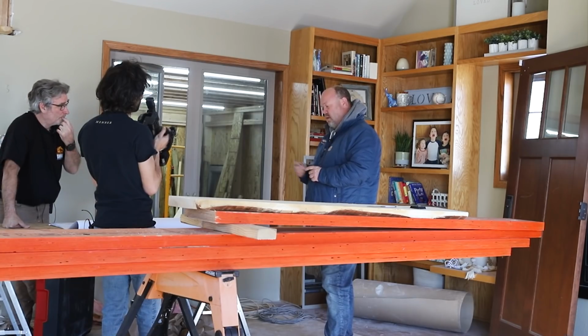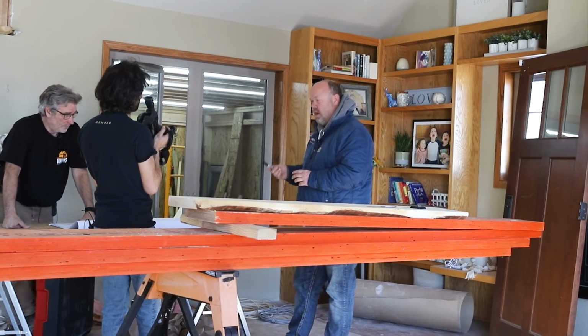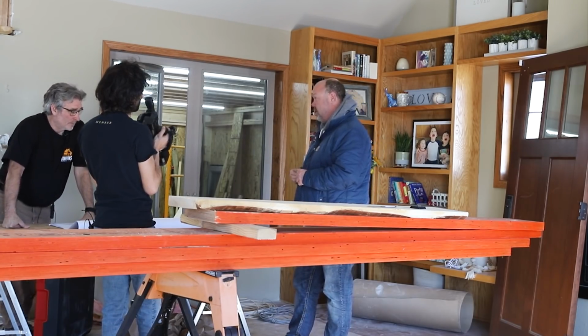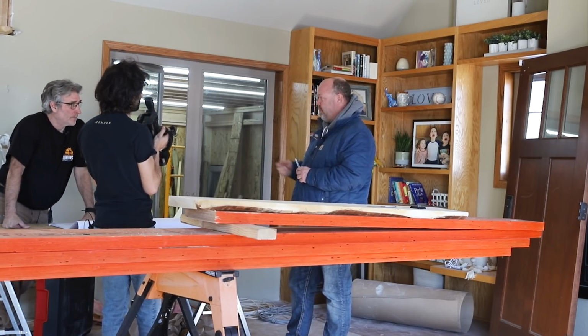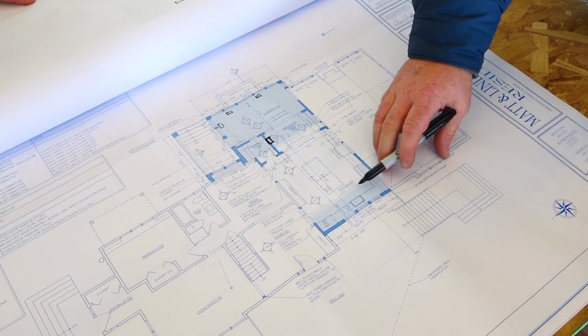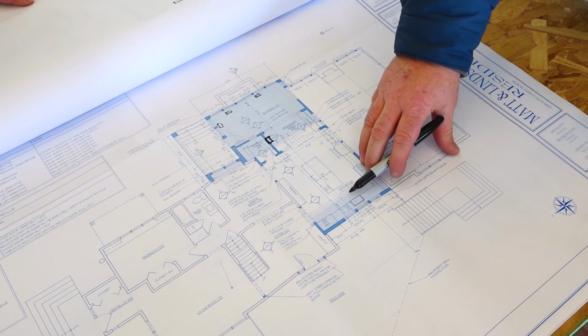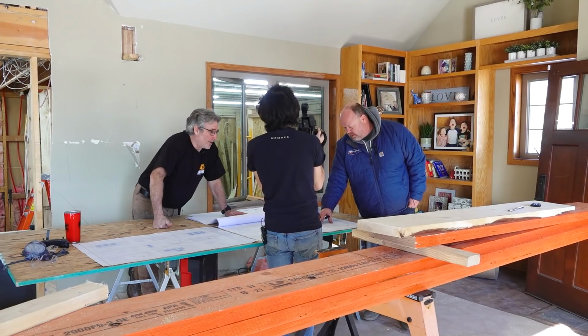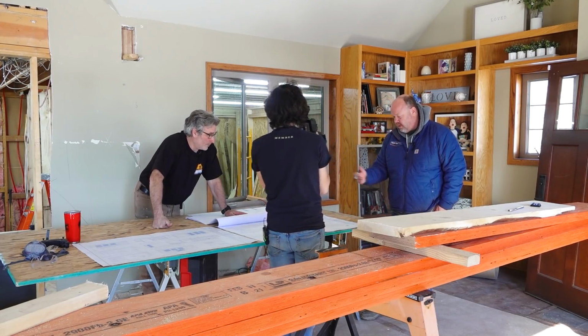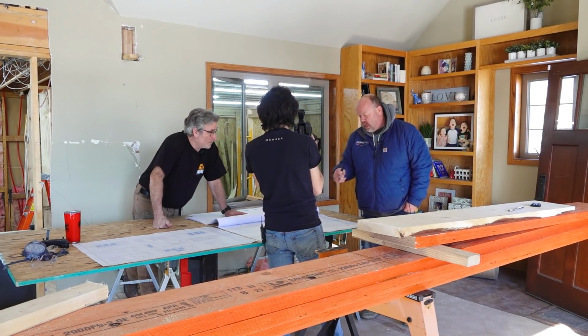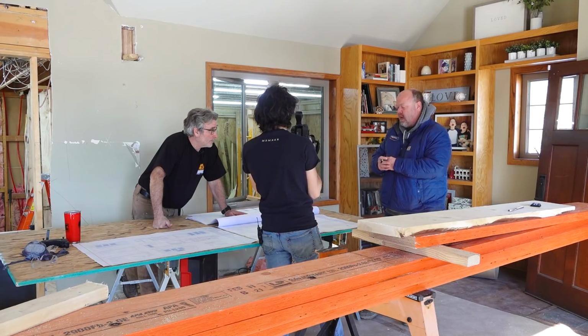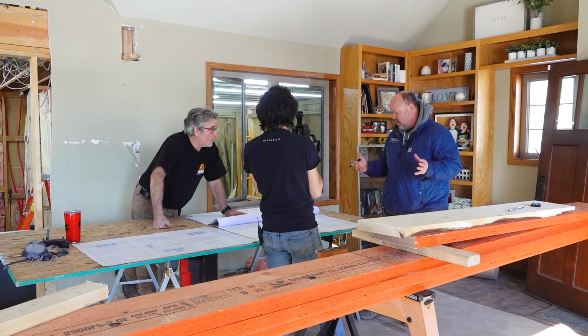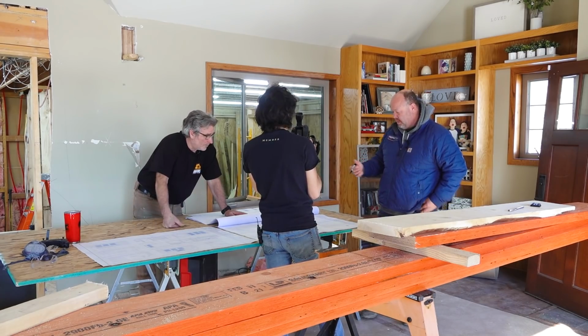If you can't get a return in a room, you do things like undercutting a door or doing a transfer grill to help promote airflow. In this situation, we can't get here with the framing. It's cantilevered out, correct? Yeah, and it's very difficult to get out there. So what we're going to do is heat without hitting the outside walls. We just have to make sure we have enough volume of air to deliver the BTUs we need.